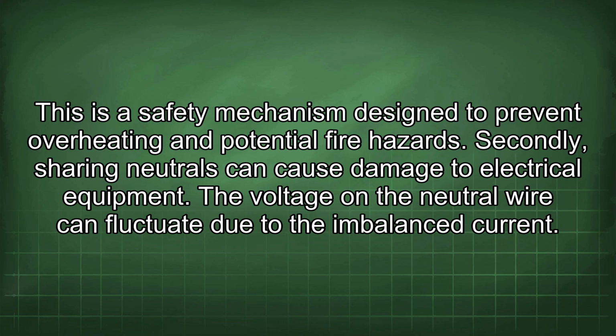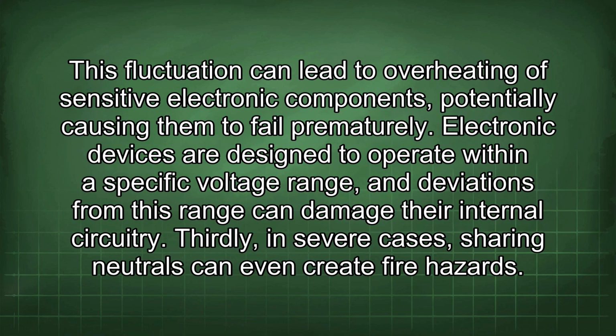Secondly, sharing neutrals can cause damage to electrical equipment. The voltage in the neutral wire can fluctuate due to the imbalanced current. This fluctuation can lead to overheating of sensitive electronic components, potentially causing them to fail prematurely. Electronic devices are designed to operate within a specific voltage range, and deviations from this range can damage their internal circuitry. Thirdly, in severe cases, sharing neutrals can even create fire hazards.